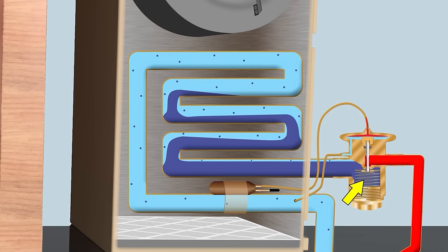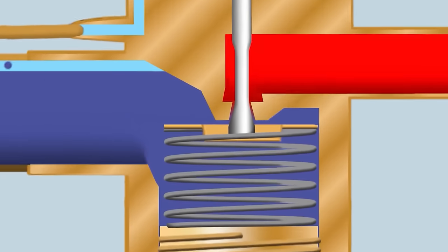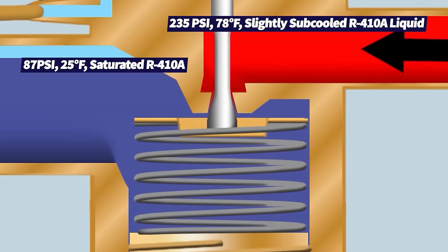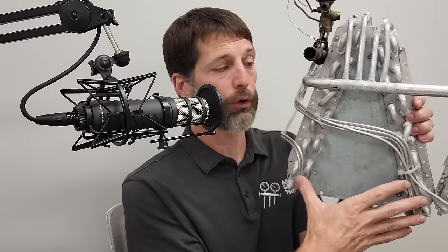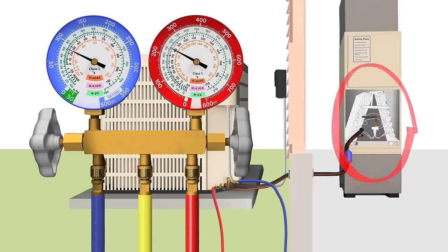If you have a low refrigerant charge and liquid refrigerant is entering the metering device, the restrictor is going to lower the pressure too much. Your saturated refrigerant — a mixture of vapor and liquid — is going to be too low in pressure as it enters the coil, and it's going to end up freezing the entire coil.